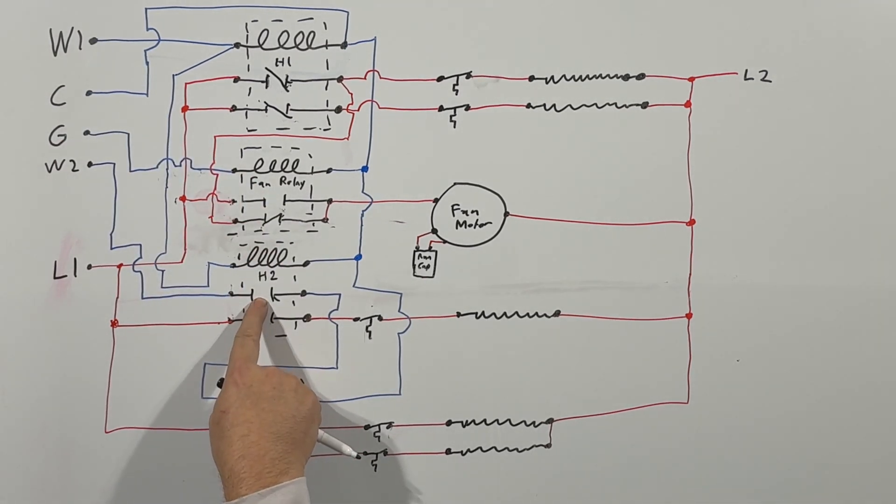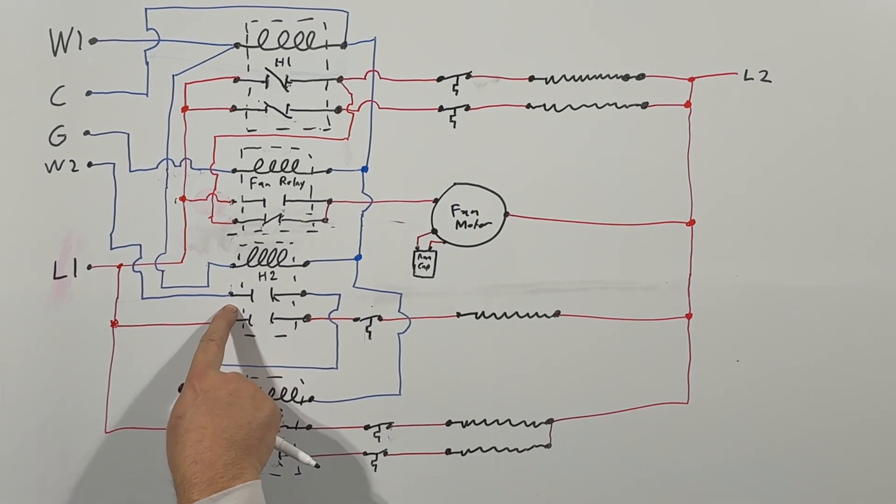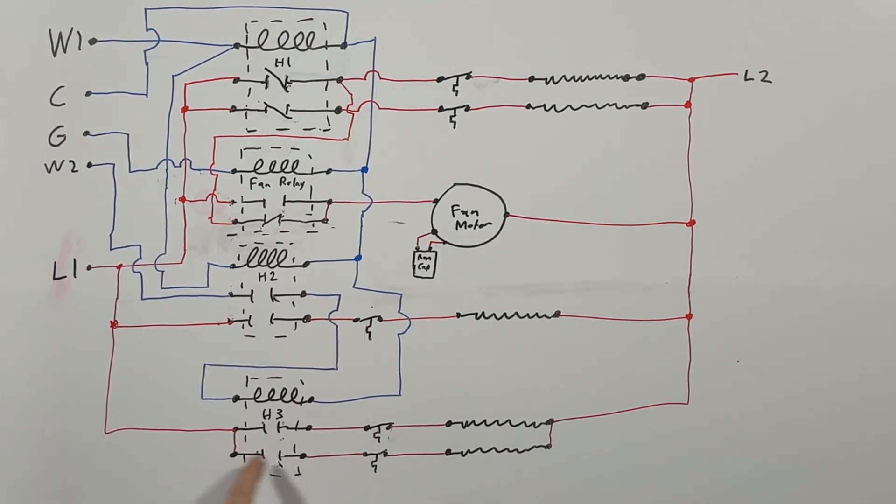So if you wanted to call for heating two or W2, you could only... it'll only do something if you're calling for W1. So if you have no... if you have not energized W1, these contacts will stay open, right?